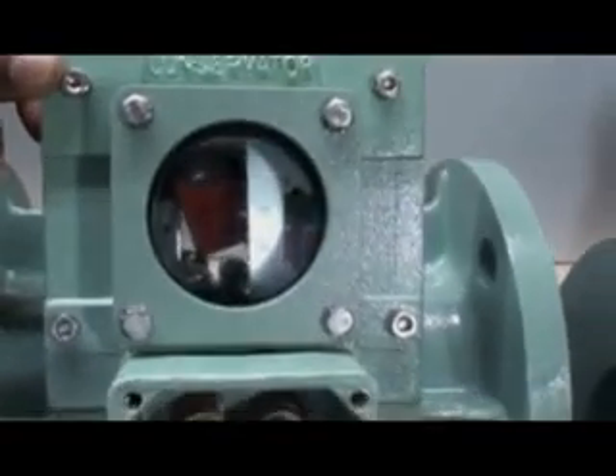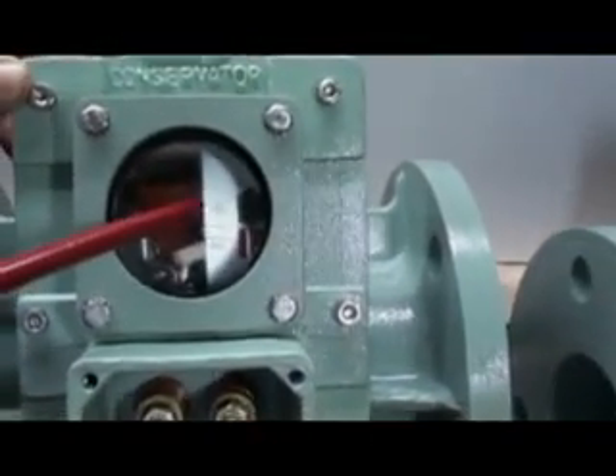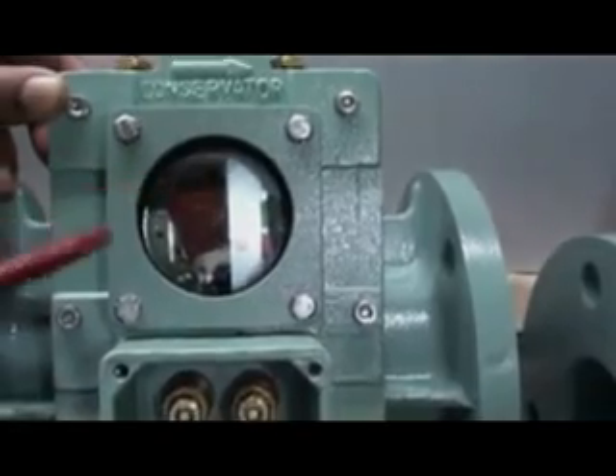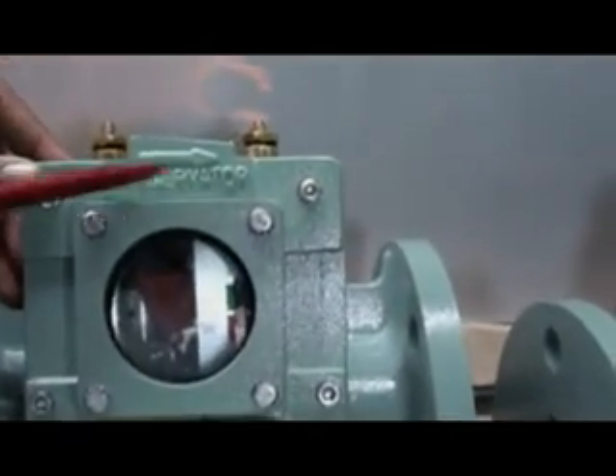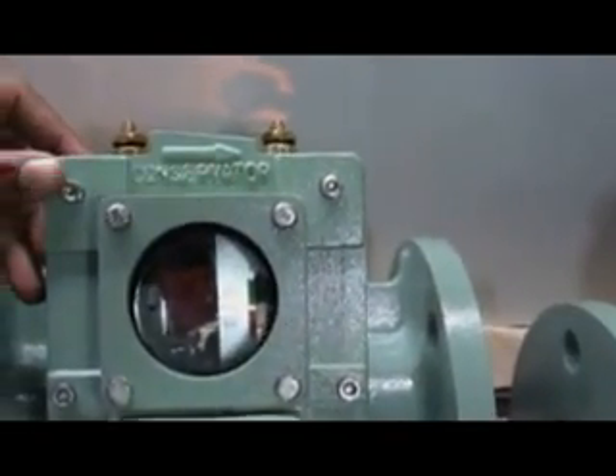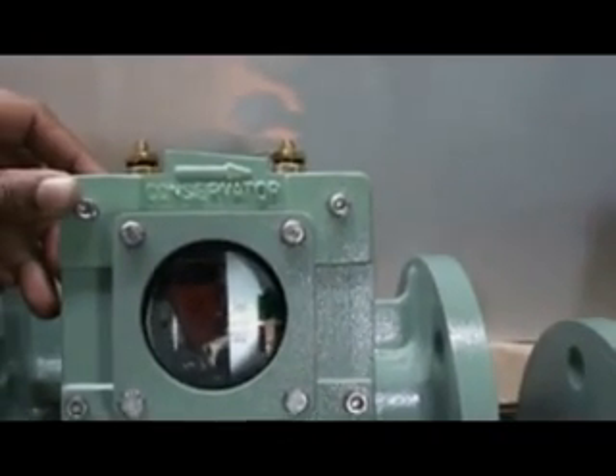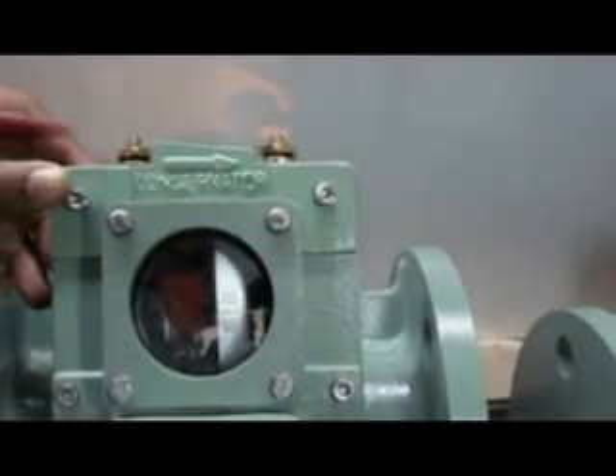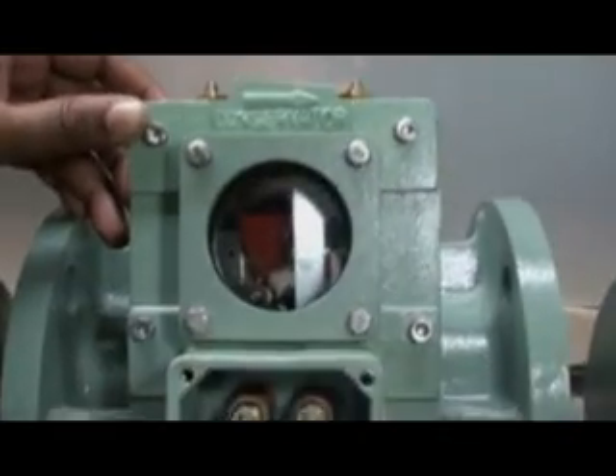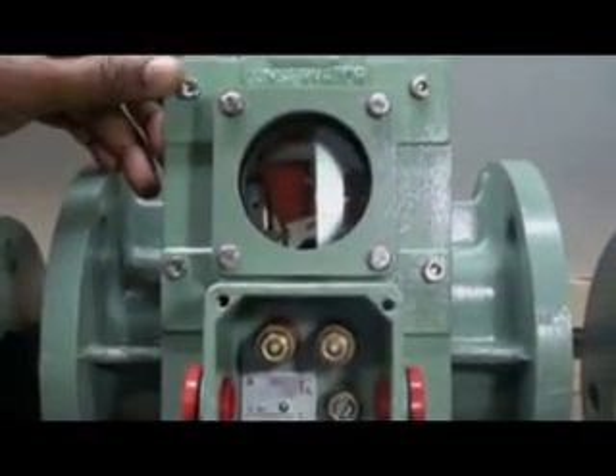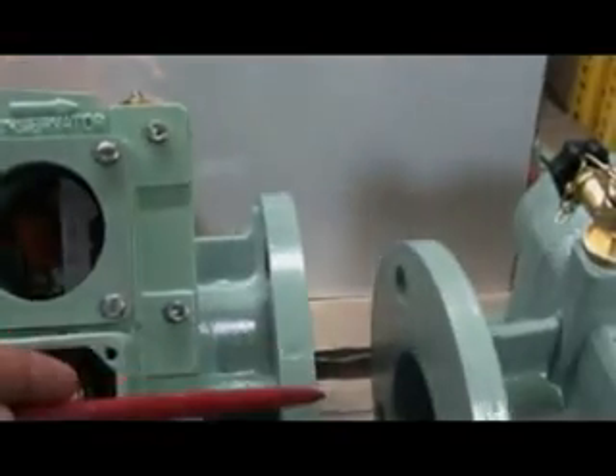If you see the glass window of the Buchholz relay, there is a scale showing gas volume. On the top, it is engraved Conservator with a direction arrow. Forward direction of arrow directs conservator pipe connection. End of the arrow shows transformer tank side pipe connection.